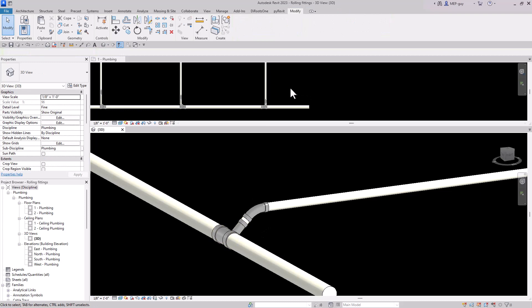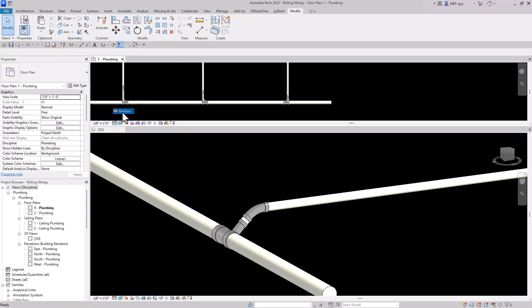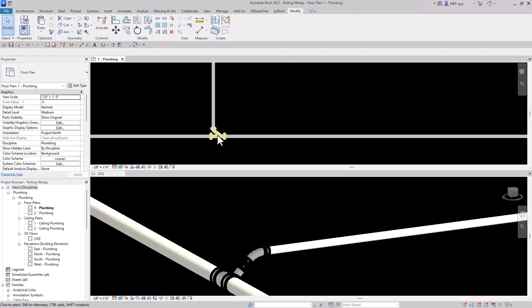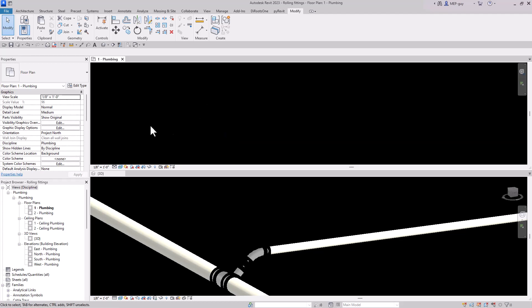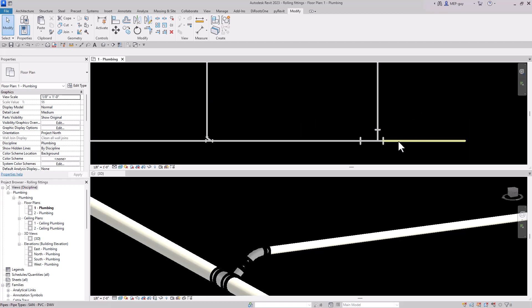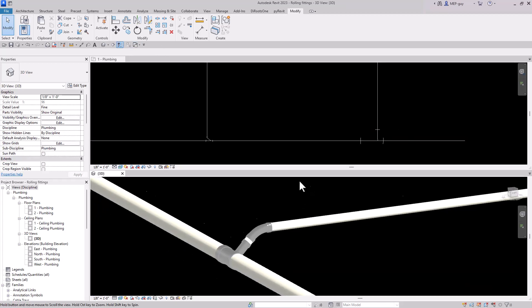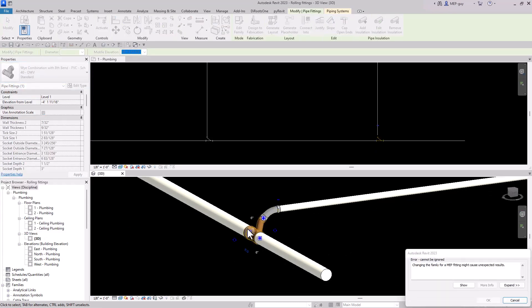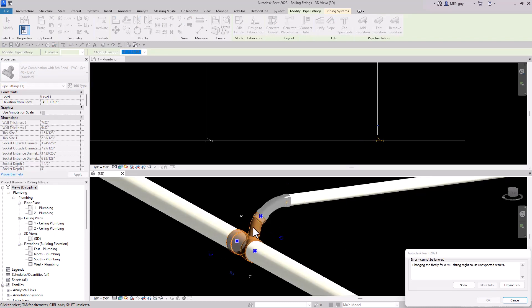Here's the problem: looking at this in a floor plan at medium level of detail, the other pieces have a nice slope or angle showing the flow direction. But this fitting is a no-go — it doesn't look right. We need to change this fitting to the combo Y, but Revit will warn us because there isn't enough room to fit the combination Y fitting and the elbow fitting together. So we have to come up with another solution.